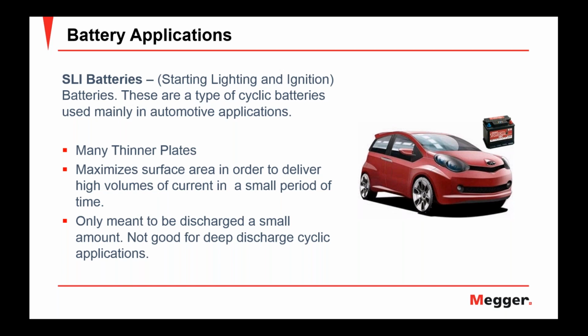So these type of batteries have a lot of very thin plates to maximize surface area that are very close together. They have very small separators in between them. They're very thin, and they're under compression.